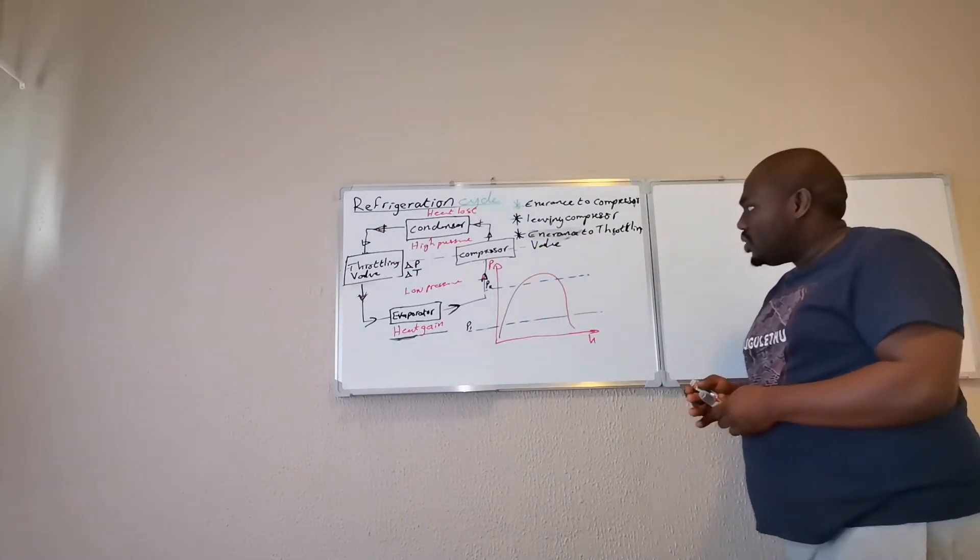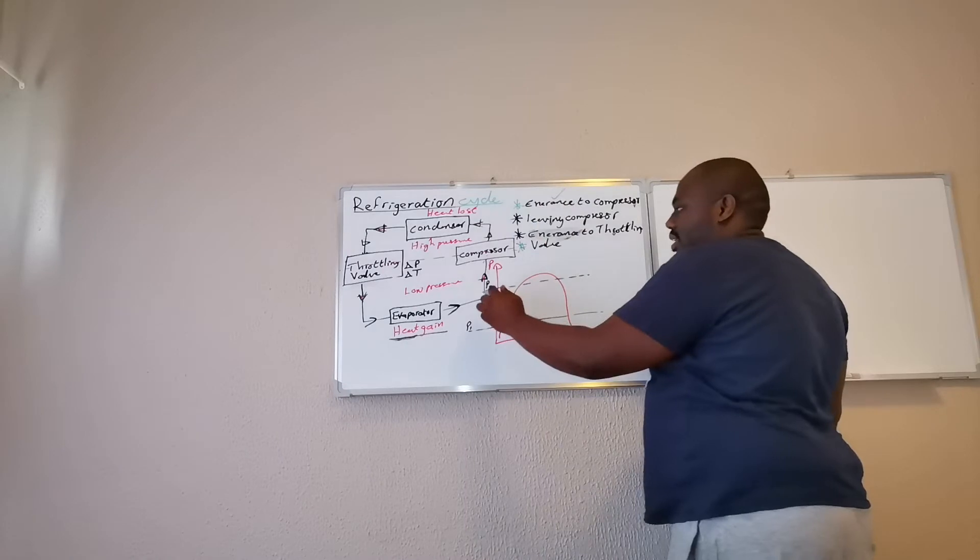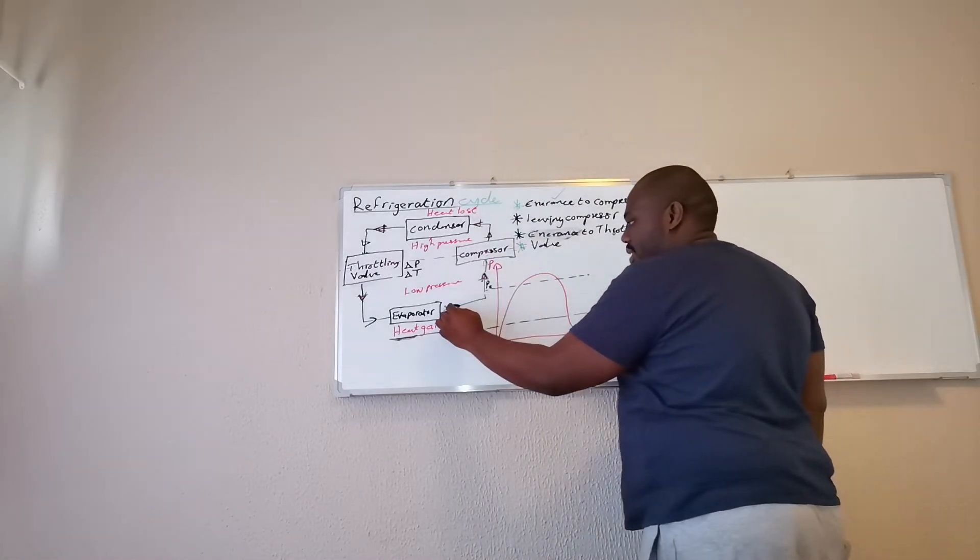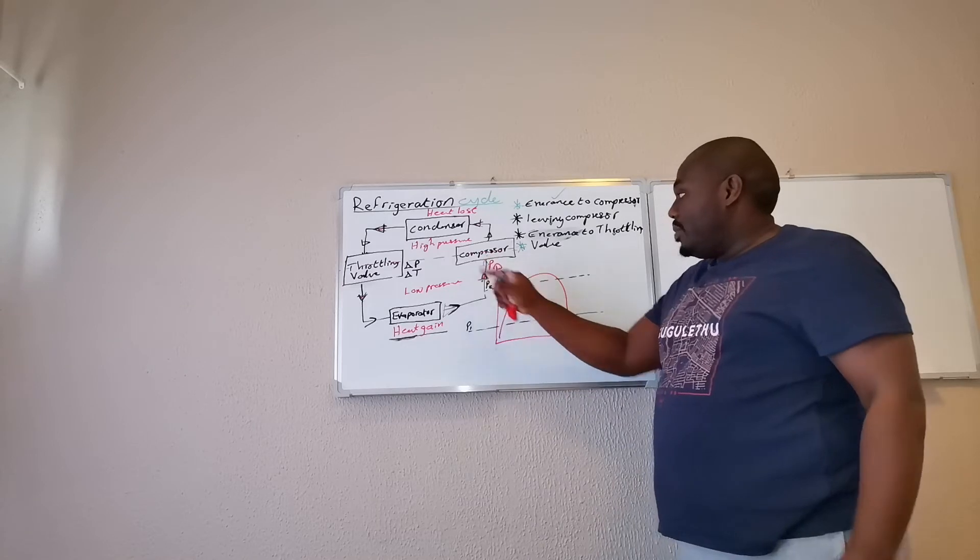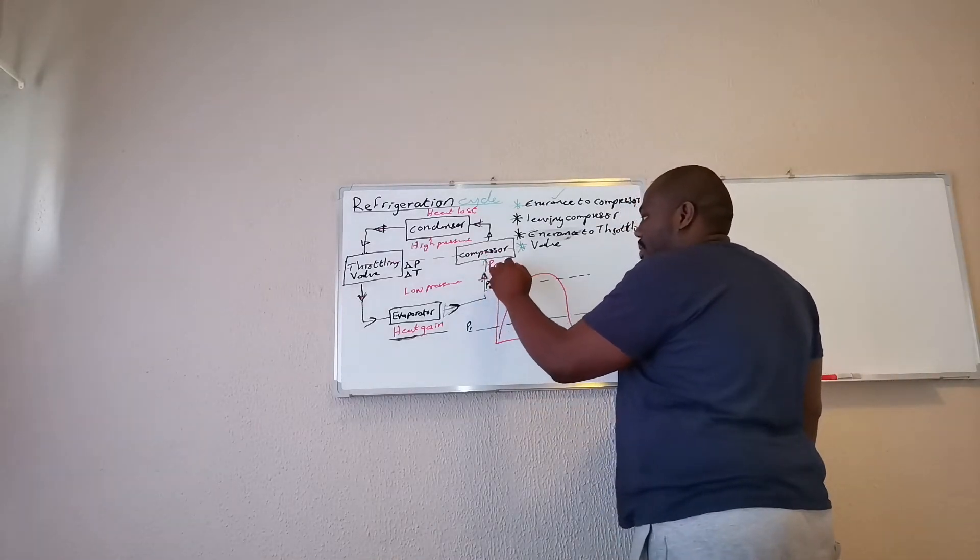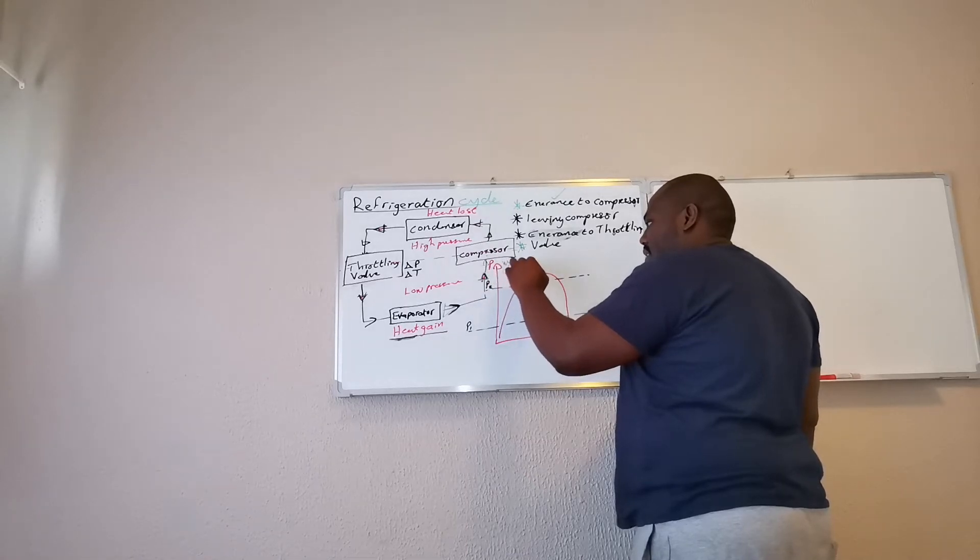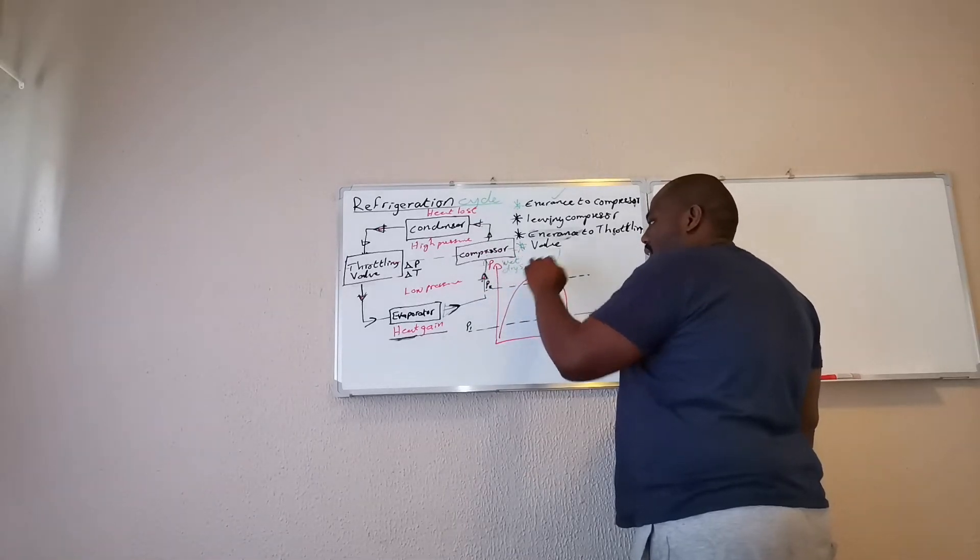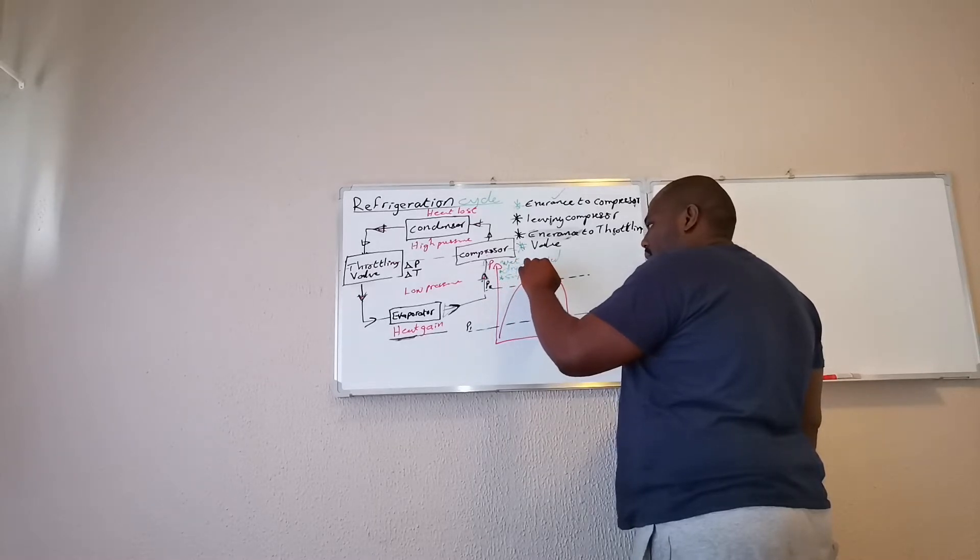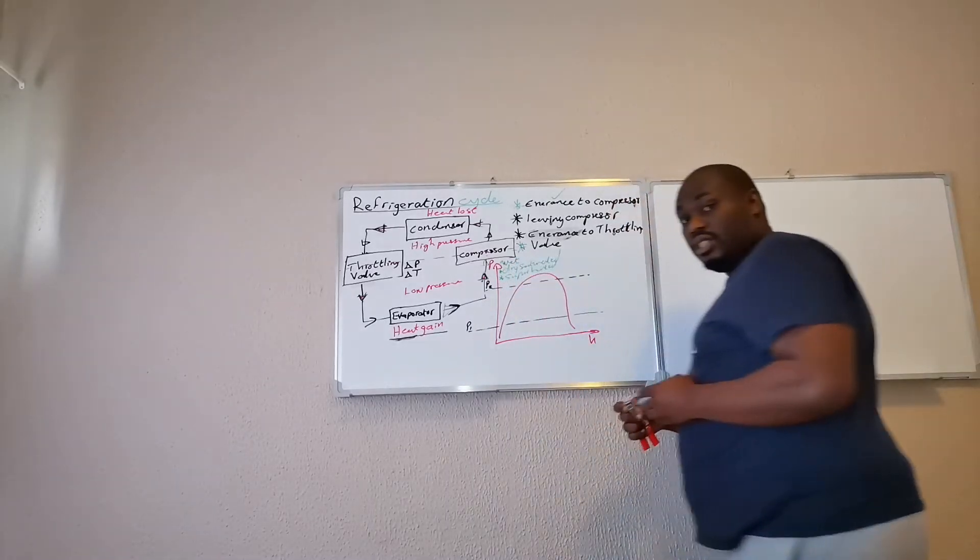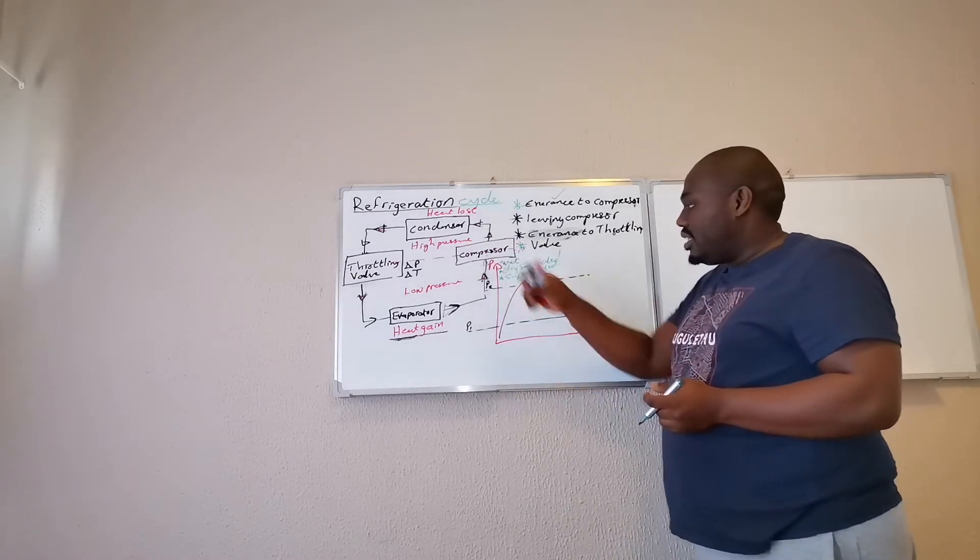So starting with the first one, entrance to the compressor. So this is going in there. So if it's going in there, it means it was exiting my evaporator. So there are three ways in which my refrigerant can enter my compressor. It can either enter your compressor wet, it can either enter your compressor dry saturated, or can either be superheated. So those are the three types that your refrigerant can enter your compressor.